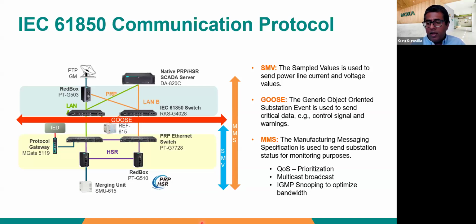Now, just like we talked about in the last slide, not all these data streams are urgent and important. So you need to have a prioritization to maintain a certain quality of service. For example, GOOSE messages in the IEC 61850 protocol will get the highest priority, because those are expected to be typically some control action, versus an MMS that may have a lower priority. And the way the architecture is, it's multicast, which means the information is spread across. Obviously, you can choose to make the information flow only between certain devices. You can approach it using techniques like IGMP snooping, but otherwise, by default, the information is multicast, sent to all the devices in the network.